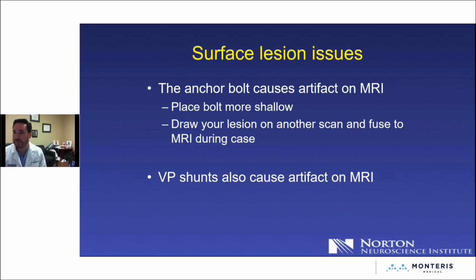VP shunts, by the way, also cause artifact. And I learned this the hard way when I had a kid who I wanted to laser a lesion on the right. His shunt was on the left. I looked at a bunch of MRI scans ahead of time and basically proved to myself that there's not a lot of artifact where I want to target from this shunt valve. I said I'm good to go, and I got in, and on the Monteris scans, there was horrible artifact. So shunts will also cause artifact, even if they're a distance away. Just something to know. What we did in that case was we very uncomfortably did timed burns, where we would laser for a bit, stop and get a scan, and then pull back. We saw what we saw after 5 minutes of lasering, and then said, okay, empirically, I'll pull back and do 4 minutes of lasering, get a scan, and see what we see. It was a rough day, but now you know shunts will cause that artifact. It's something you need to consider.